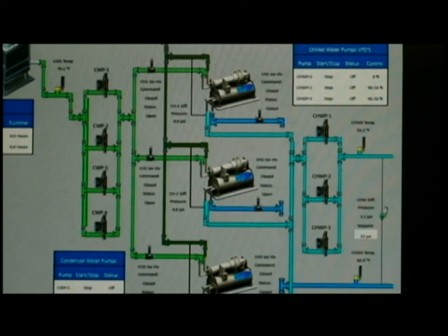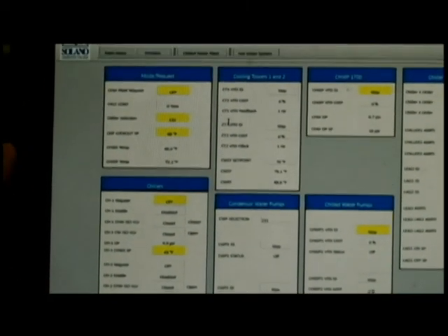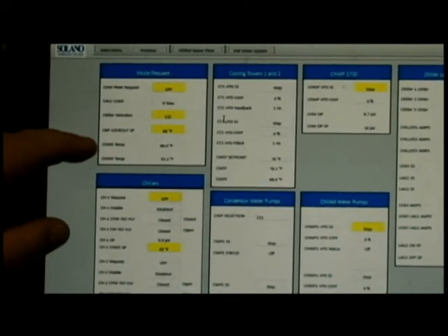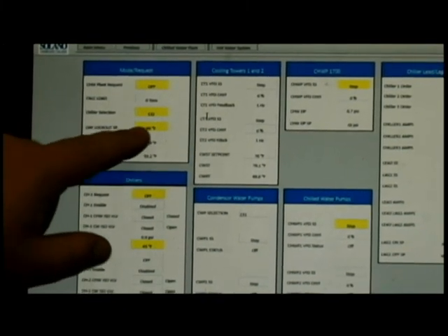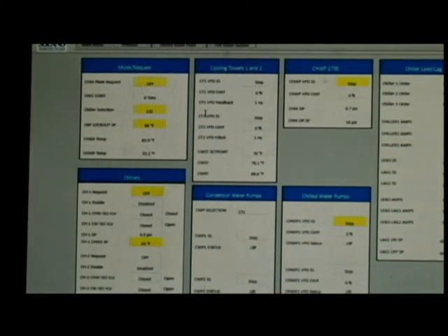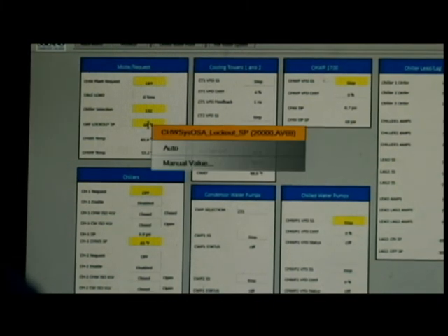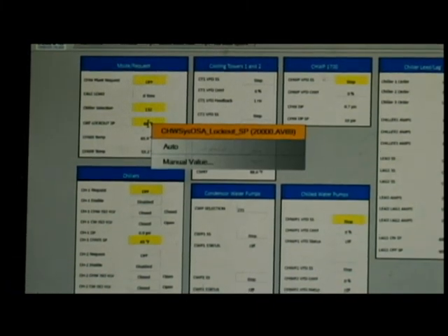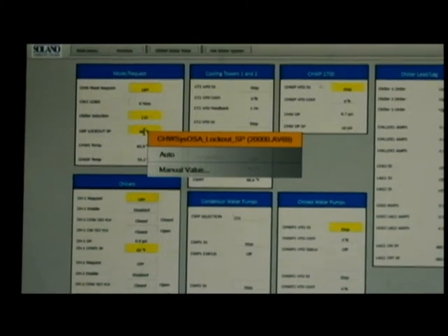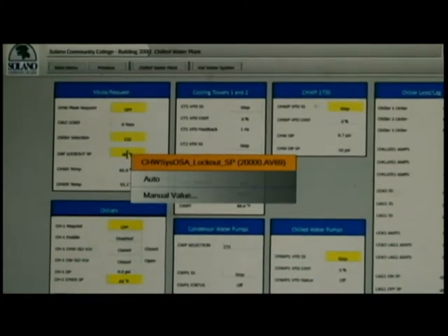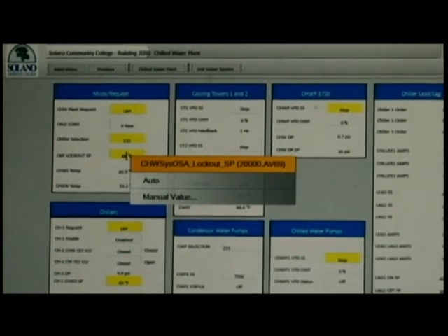If you need to make any changes in here, the web interface is pretty simple for making adjustments to anything. There's a couple ways you can do it. We can make an example here of our outside air lockout. So here we're looking at the chilled water system settings again, and we have our outside air lockout set point, which is this little object right here. You can hover over it with your mouse, and you can do this with any object in here. Basically any point on the system, you're going to get a little menu that pops up just by hovering over that point in the graphic.